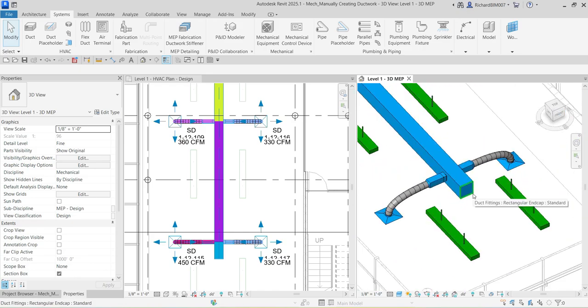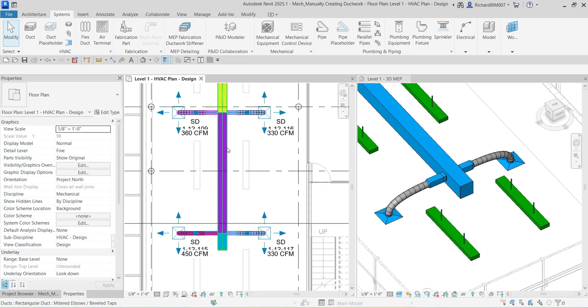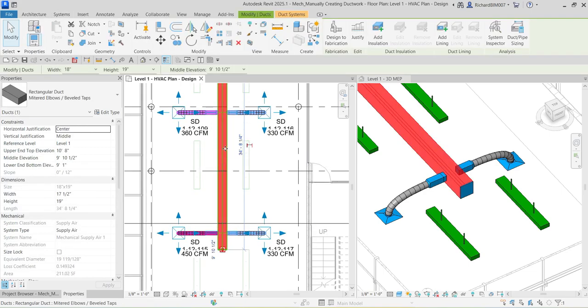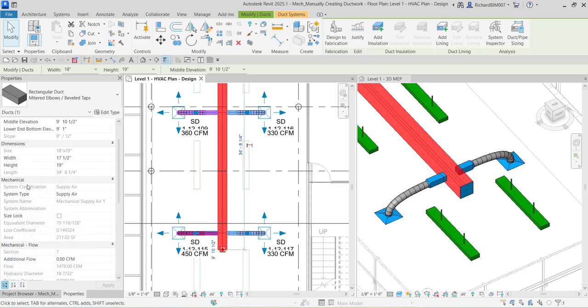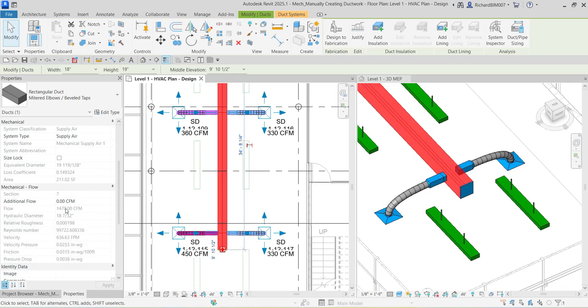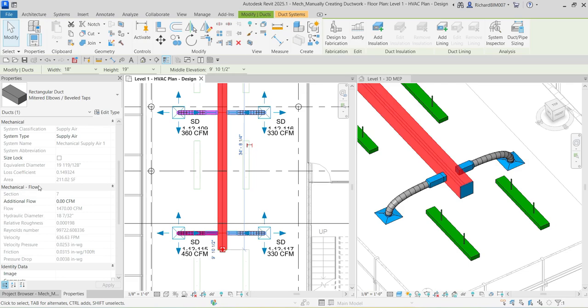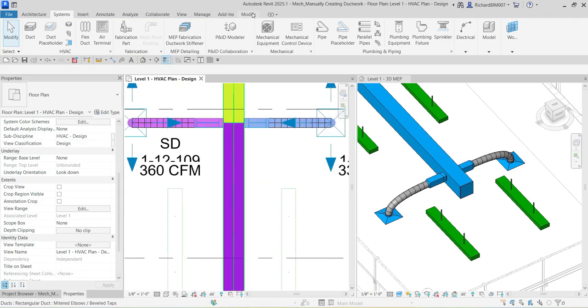Now it's time to size our main duct. I'll show you how to split and size it. Clicking the main duct and checking the Mechanical properties shows the actual airflow — it's 1470 CFM, which is the sum of 360, 330, 450, and 330 CFM from all diffusers. This tells us the total flow being supplied to the main duct.